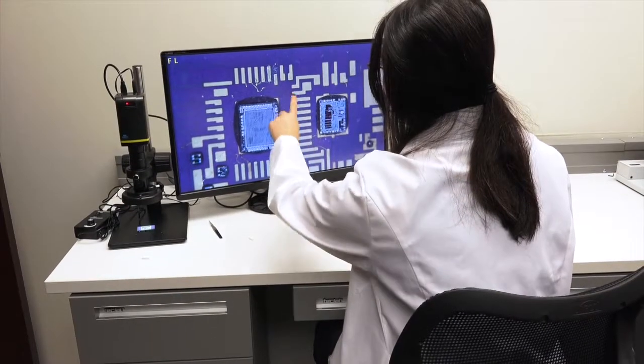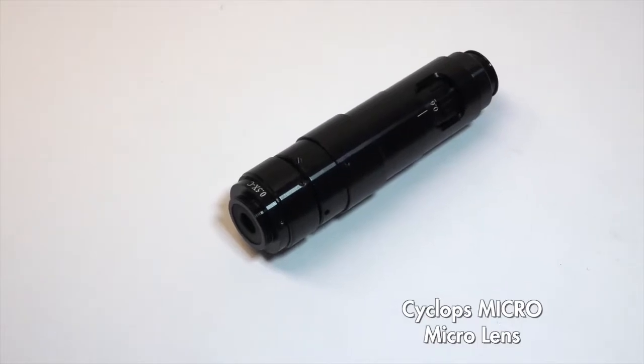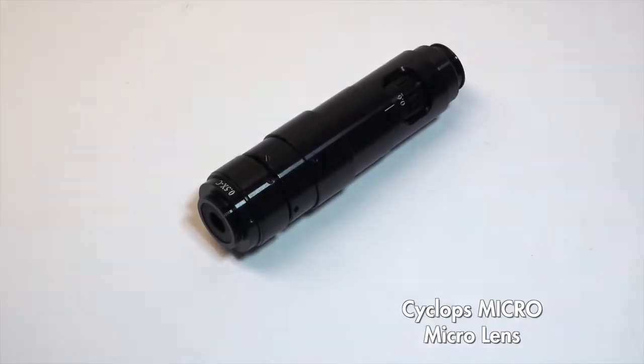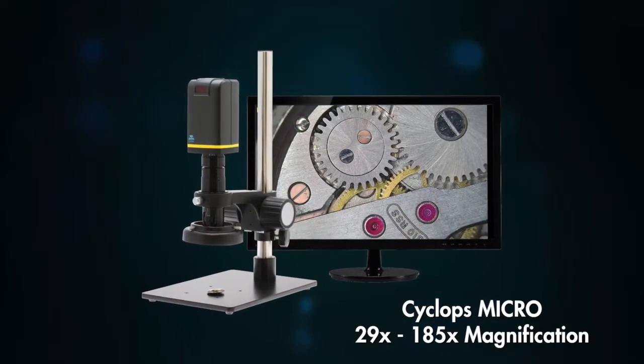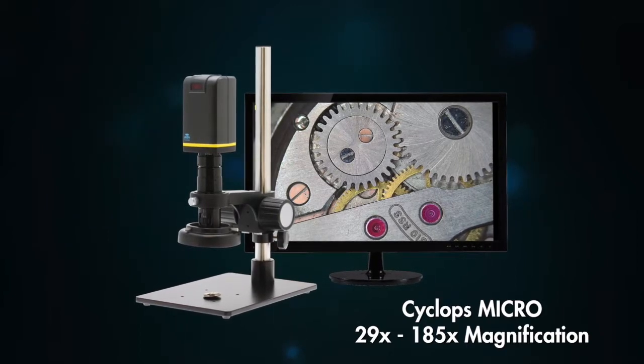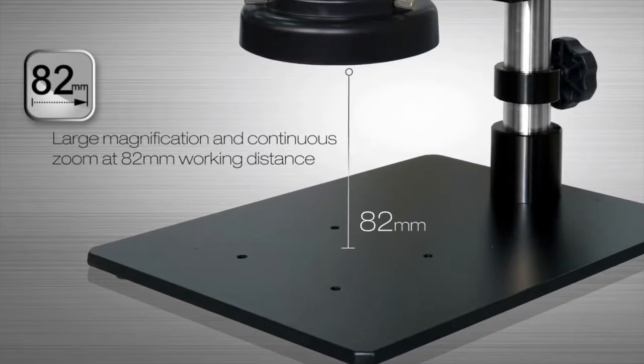For applications that require a closer look, the Cyclops Micro system includes an optical micro lens offering a magnification range of 29x to 185x at a working distance of 82mm.